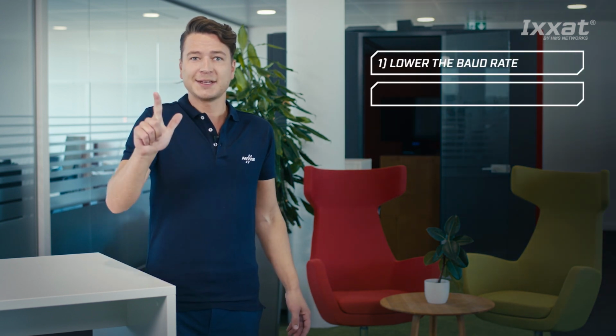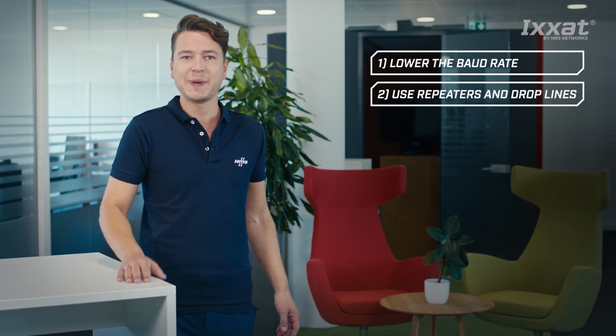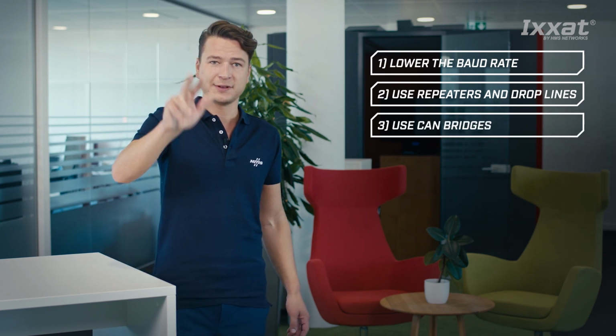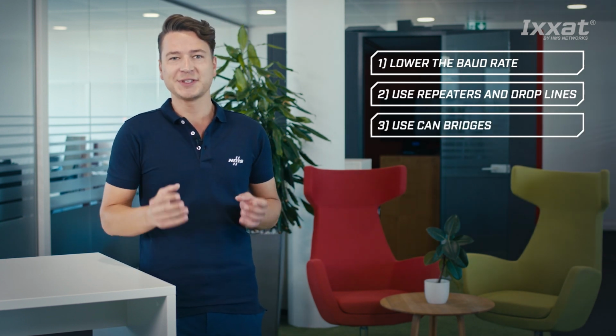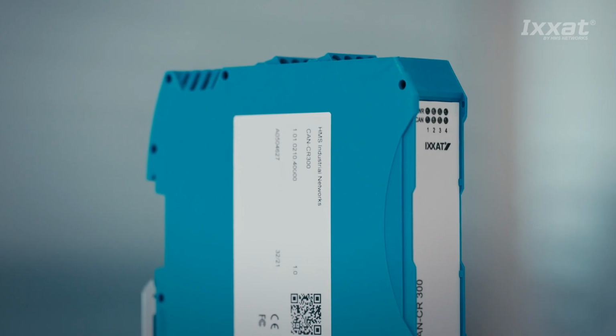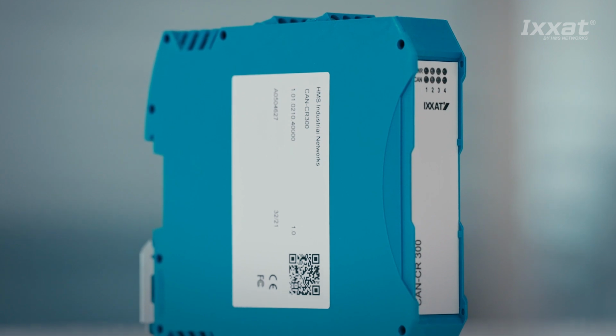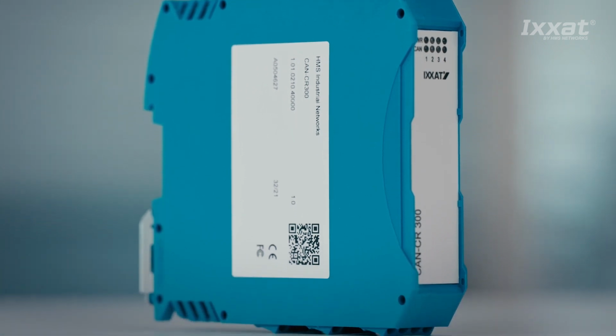First, you lower the baud rate. Second, you improve the cable routing by using repeaters and drop lines, or third, you expand the bus by using CAN bridges. We need to make a distinction here. CAN repeaters do not allow extending the maximum length, but instead intelligent routing often saves cable length. You adapt the bus to the best system structure with drop lines.